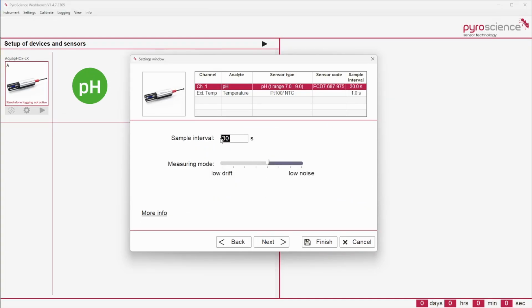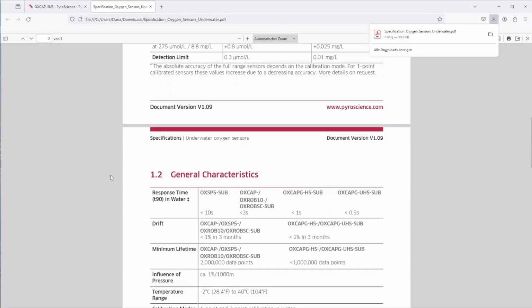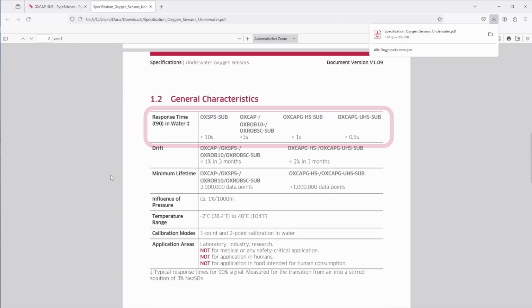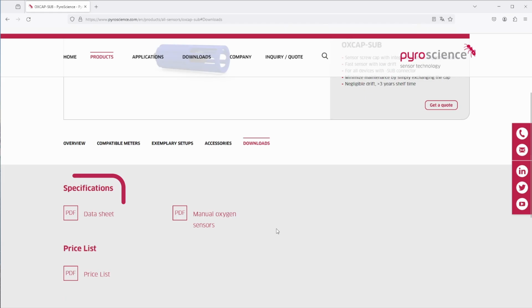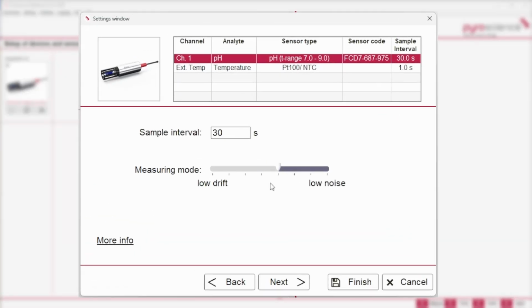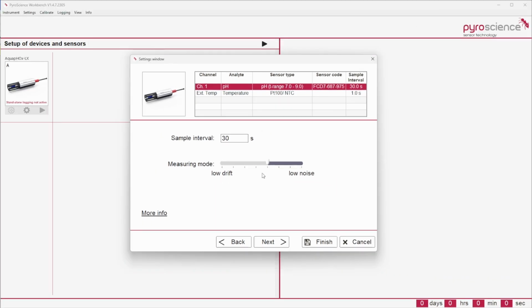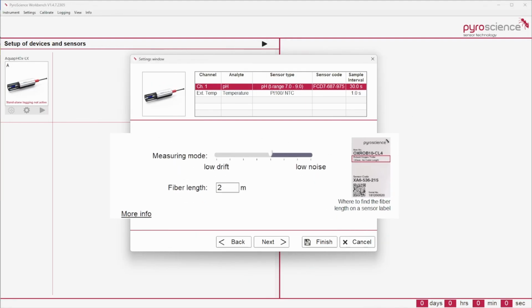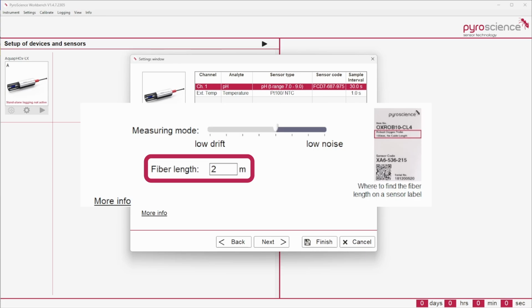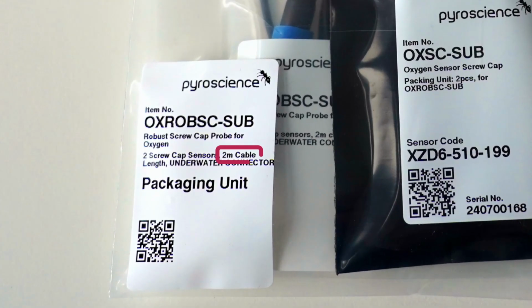The minimum intervals for each sensor type are listed in the datasheet with respective specifications, which can be found in the download tab of the product page. The setting low drift can be selected in case of long-term measurements. For short-term precision measurements, low noise is preferred. However, this configuration will shorten the lifetime of the sensor. In general, it is recommended to keep the pre-adjusted settings. For fiber sensors, enter the cable length of your fiber for a correct readout. The cable length can be found on the package.